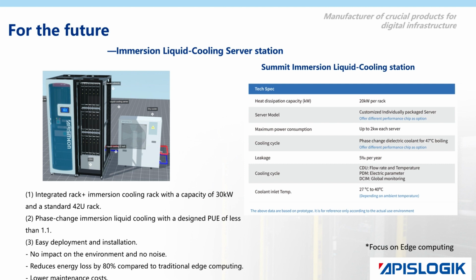As mentioned above, there is no particularly effective energy-saving solution in tropical regions. Therefore, we are currently developing our next-generation, fully immersed liquid-cooled micro data center. With a single cabinet, it can achieve a capacity of 30 kilowatts and a PUE of less than 1.1. This solution can be used even in tropical or desert areas while achieving energy-saving goals.